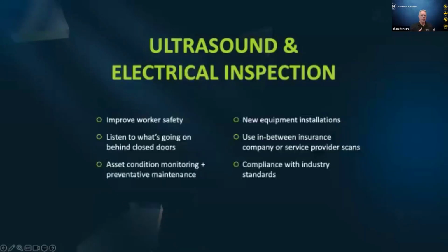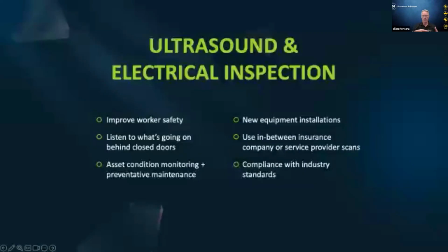By allowing inspectors to listen to what's happening inside their closed electrical cabinets, ultrasound makes it possible to detect problems without opening energized equipment and exposing those inspectors and the people in the vicinity to the dangers of arc flash or arc blast. It also serves as a powerful condition monitoring and preventative maintenance tool. We can detect arcing, tracking and corona long before they become visible or lead to failures. These are all signs of a breakdown in the dielectric material, the insulation of different components in the electrical system. Ultrasound is especially useful during new equipment installations, helping to confirm proper operation right from the start.